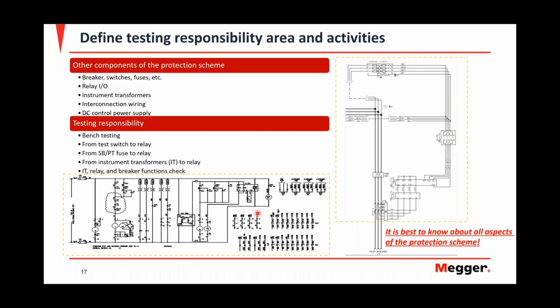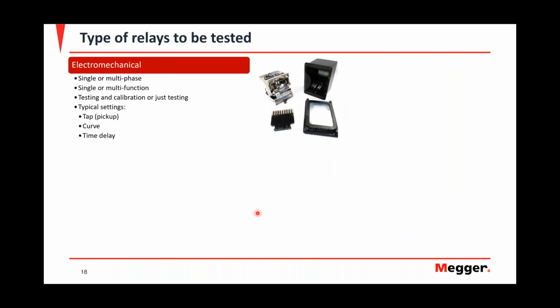So it is best to be aware that just because you're a relay tester, it does not mean that you should not be aware. The best testing guys are the guys that are aware of the whole scheme, of everything that's happening. You don't have to be an expert on every single little thing, but you should have an idea of what's going on around you in the electrical world. The types of relays that you could be testing: I'm only going to talk about electromechanical and microprocessor. There are solid state relays, but usually solid state relays were made as a direct replacement for electromechanical relays. So for the time being, I'm only going to talk about electromechanical and microprocessor.